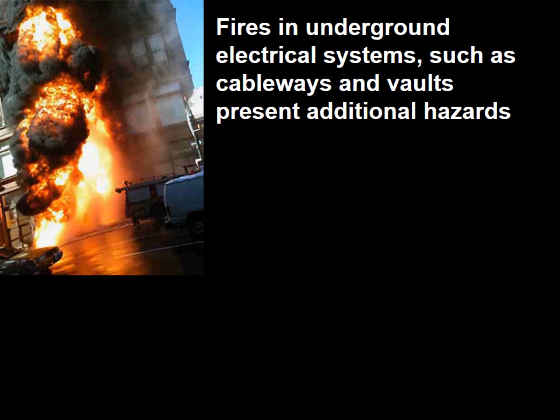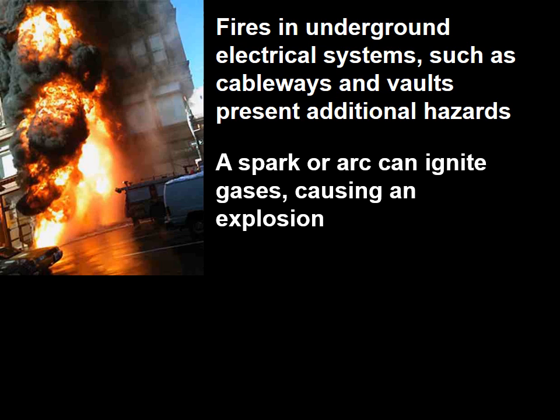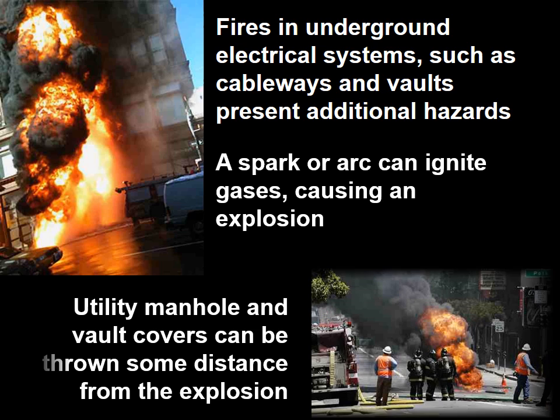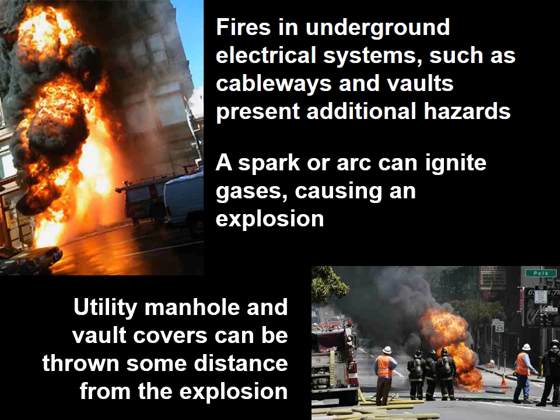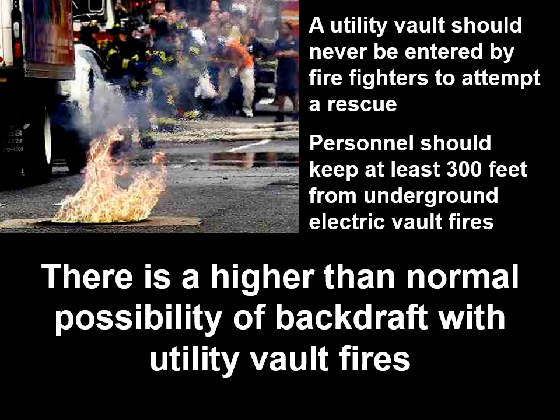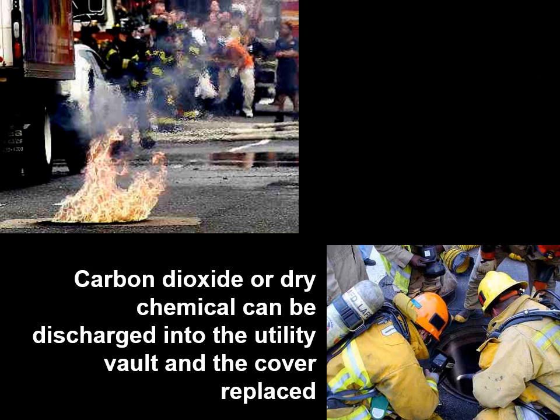Fires in underground electrical systems such as cableways and vaults present additional hazards. A spark or arc can ignite gases, causing an explosion. Utility manhole and vault covers can be thrown some distance from the explosion. A utility vault should never be entered by firefighters to attempt a rescue. Personnel should keep at least 300 feet from underground electric vault fires. There is a higher than normal possibility of backdraft with utility vault fires. Carbon dioxide or dry chemical can be discharged into the utility vault and the cover replaced.